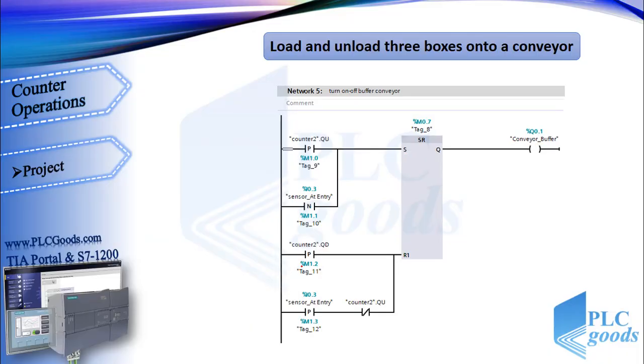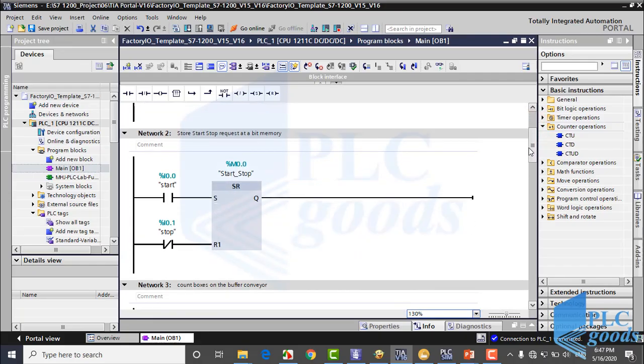Let's see my last network program to turn the buffer conveyor on and off. This network is similar to network 4. The buffer conveyor will be on if there are three boxes on the conveyor, and it will be off if it doesn't have three boxes. Also, if the first sensor detects a box, the conveyor must be on until the box is completely placed on the buffer conveyor. We don't turn off this conveyor for the third box, because all three boxes must be moved.